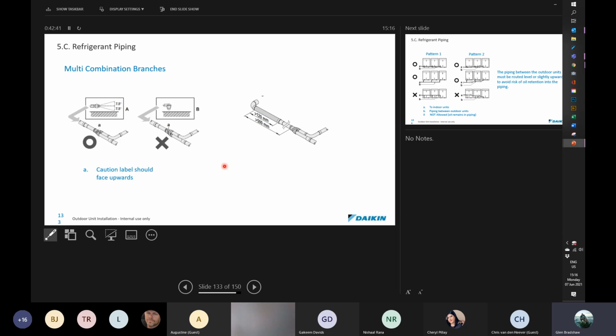Something to remember about these branch kits in the front of the unit. Okay, we all know that with VRV there are certain distance rules that are required with ref net joints. At the condenser, the only one that pertains is the 500 millimeters coming into the ref net joint from a bend. Okay, basically these ref nets, they replace the old T-pieces which were not very good or conducive to getting oil return. Ref nets do a much better job when they're installed correctly of balancing the oil return back to the compressors and the condensers, which is very important for the life cycle of the unit. These must always be mounted horizontal. That is the only way they can go. You cannot mount the pipes vertical like that, where they're one above the other, okay, or even the whole ref net joint at the condenser in the vertical plane.